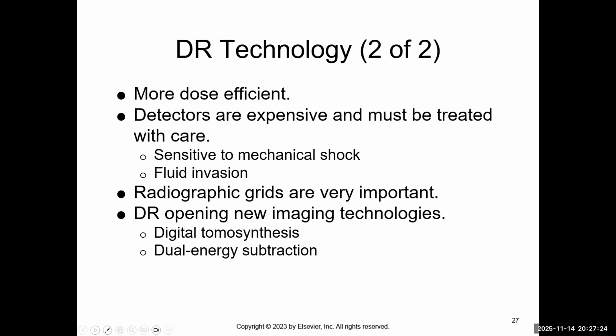And then also dual energy subtraction, which is on the C-arm type technology or fluoro technology, where I can take an image and, if I'm only interested in the vessels, let's say I shot some contrast up or I'm doing live fluoro and I want to see where maybe a blockage is, I can subtract out all of the information, just like the new technology with the cameras.